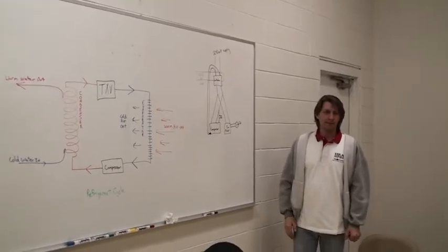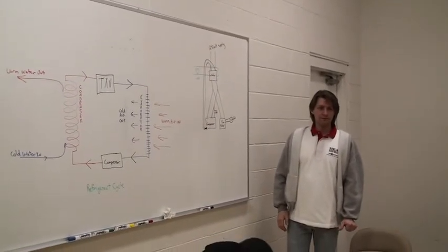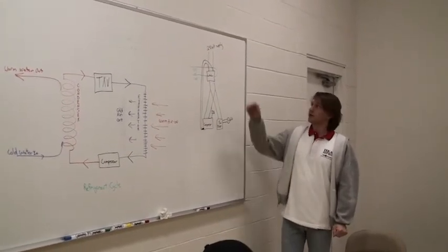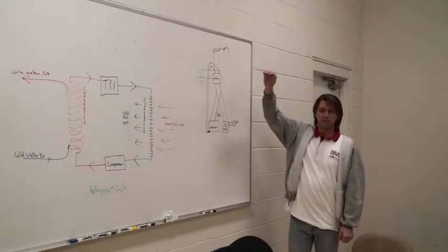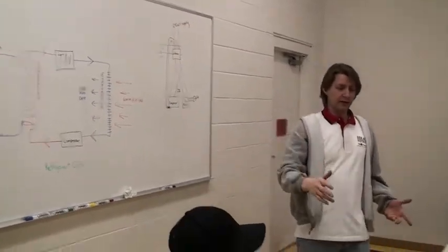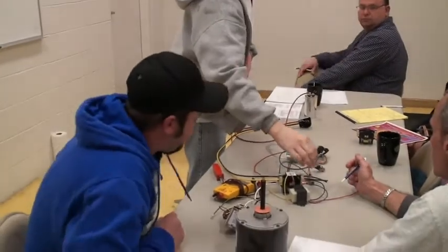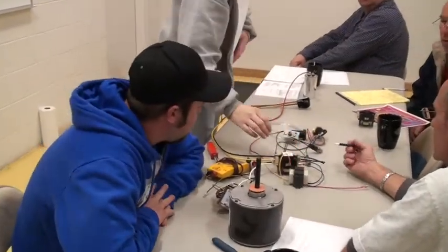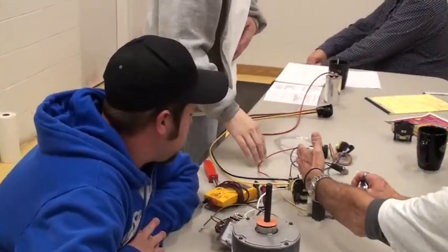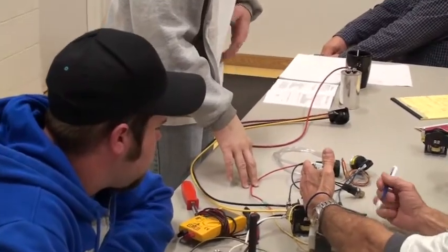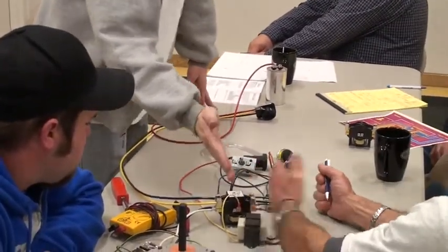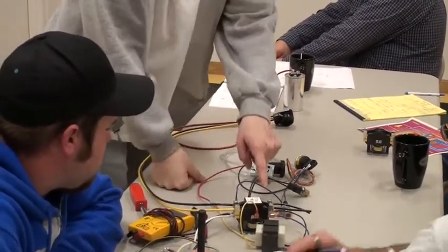There really isn't that much on the line side of that compressor. On a piston, you've got the crankcase heater and you've got the transformer, and that's it. So if we're turning the breaker on, it's important for your hand to go here too because if this lug gets burned off...